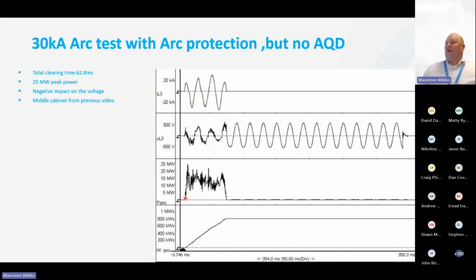In this one, this is 30 kiloamps, and this line here shows how the arc flash is seen from the transformer point of view. So this is the total power from the transformer, and the arc flash is definitely horrible looking. There is very much distortion, because an arc flash is not symmetrical in any way. The electrode is burning when you have high peaks from 3 phases. It is different. It changes in every cycle hundreds of times because the transformer doesn't actually know what it has to do. It is just burning the electrode like welding. You have to move the electrode to keep the welding ongoing. So this is the total energy for the arc flash.